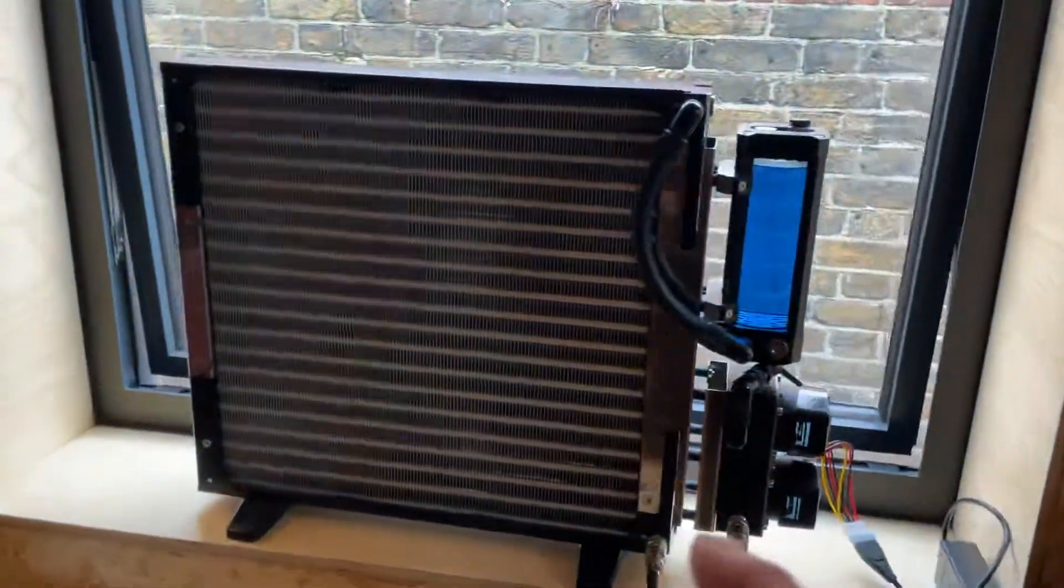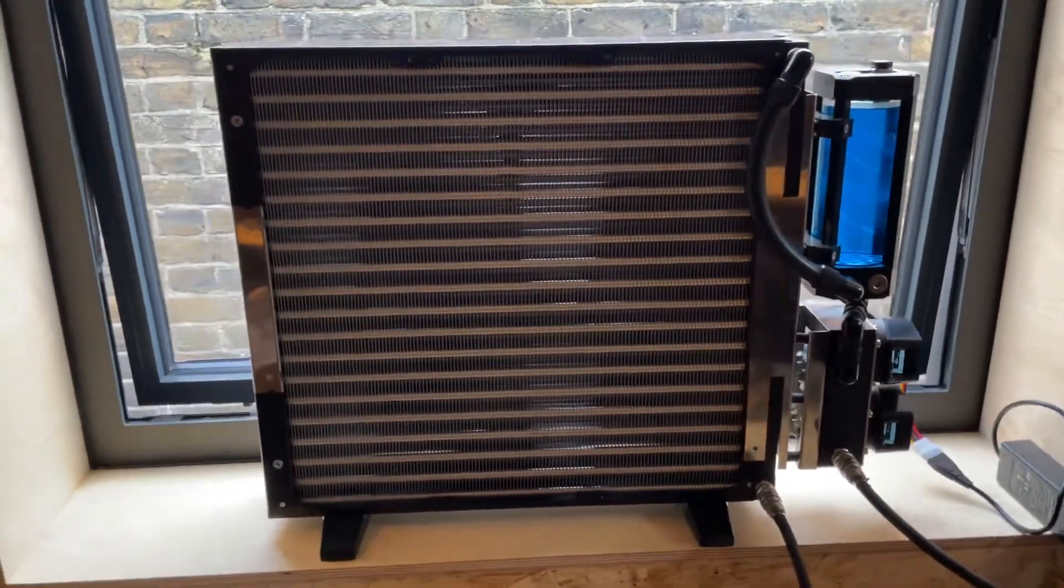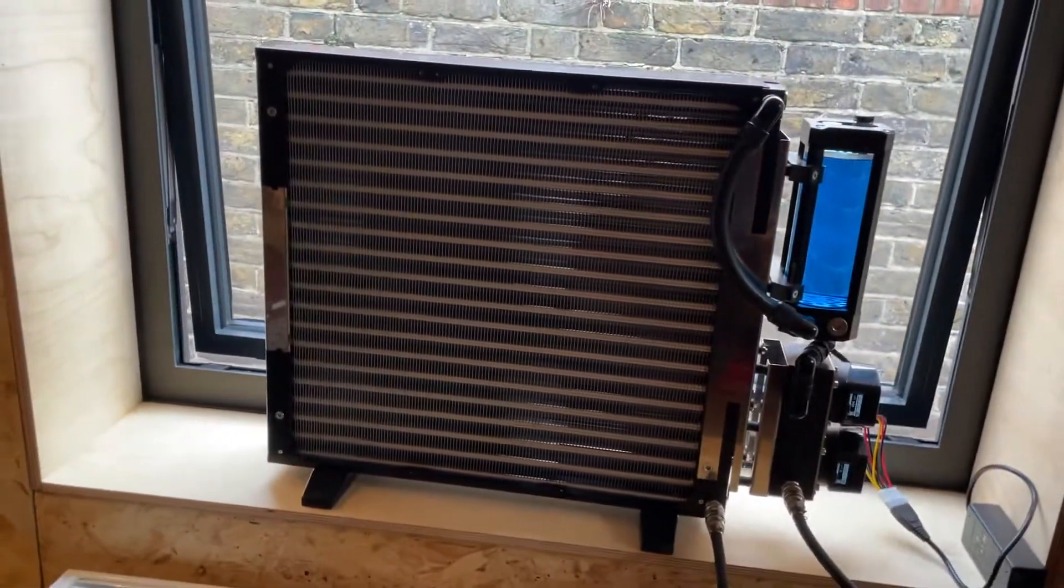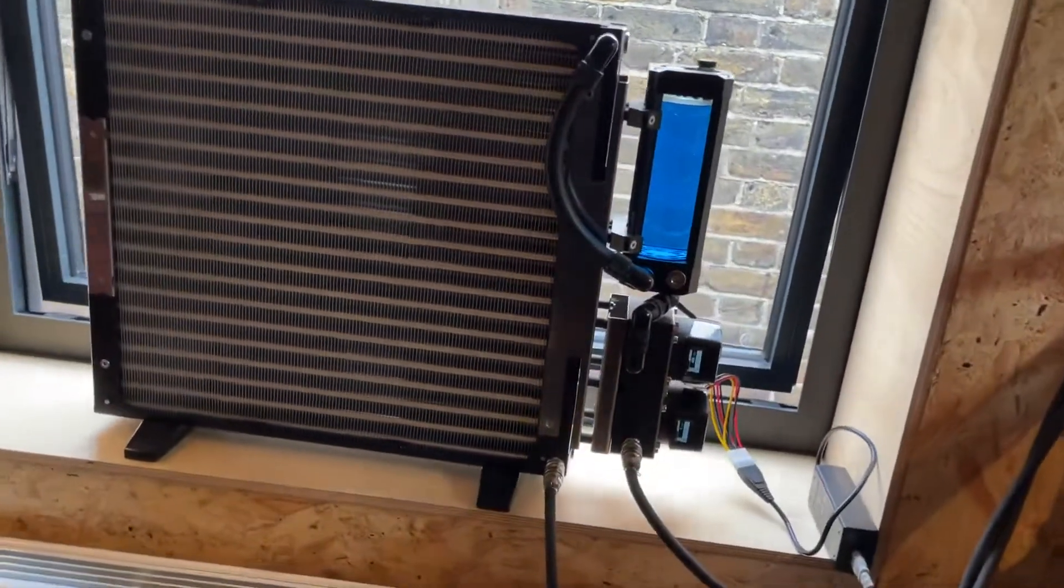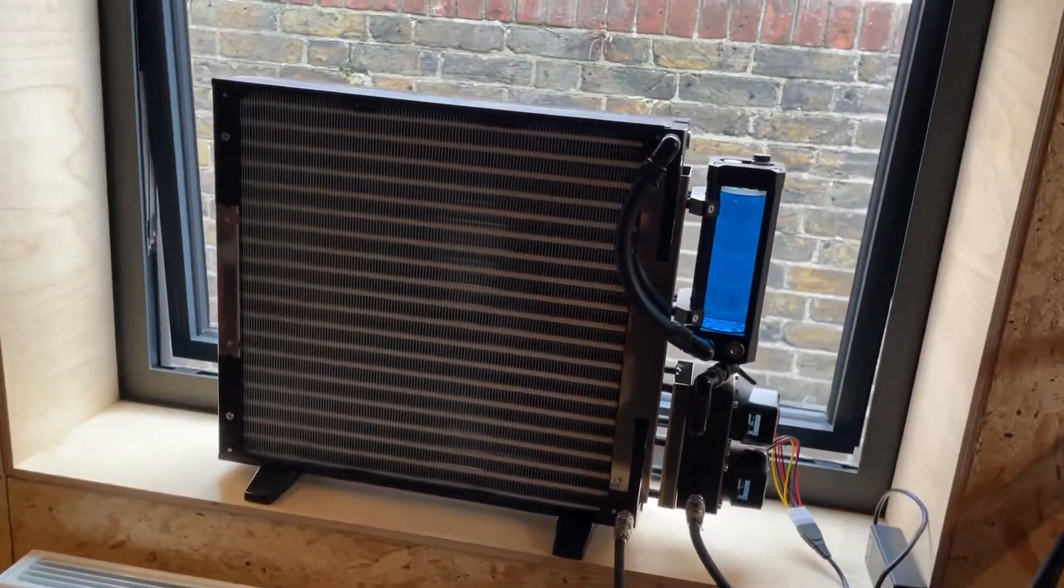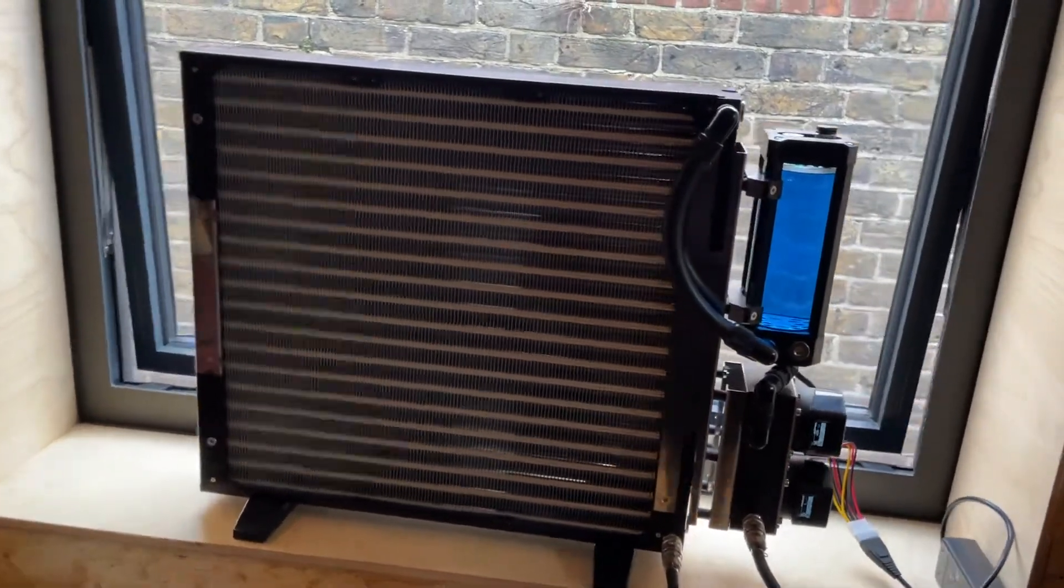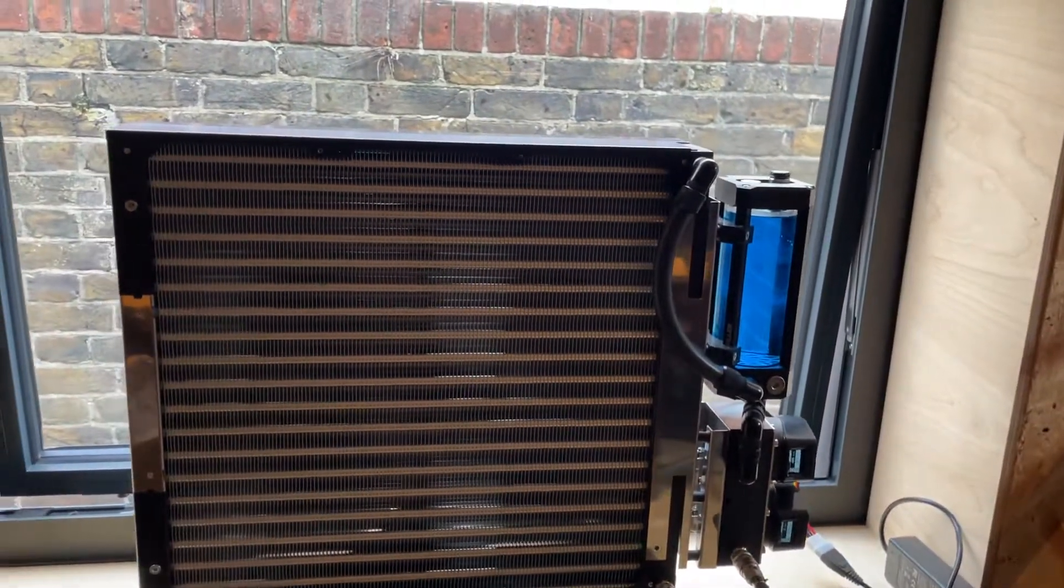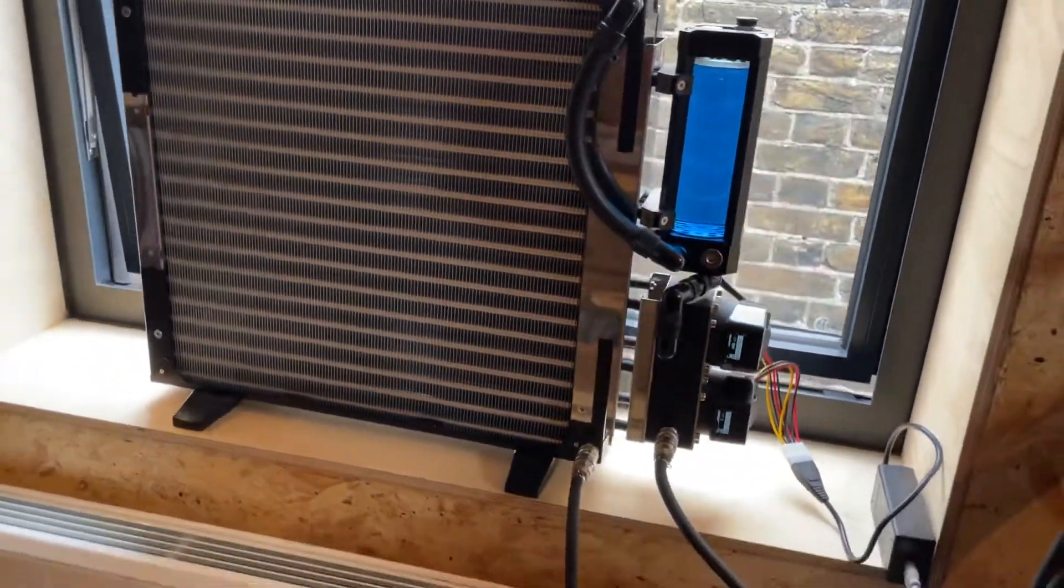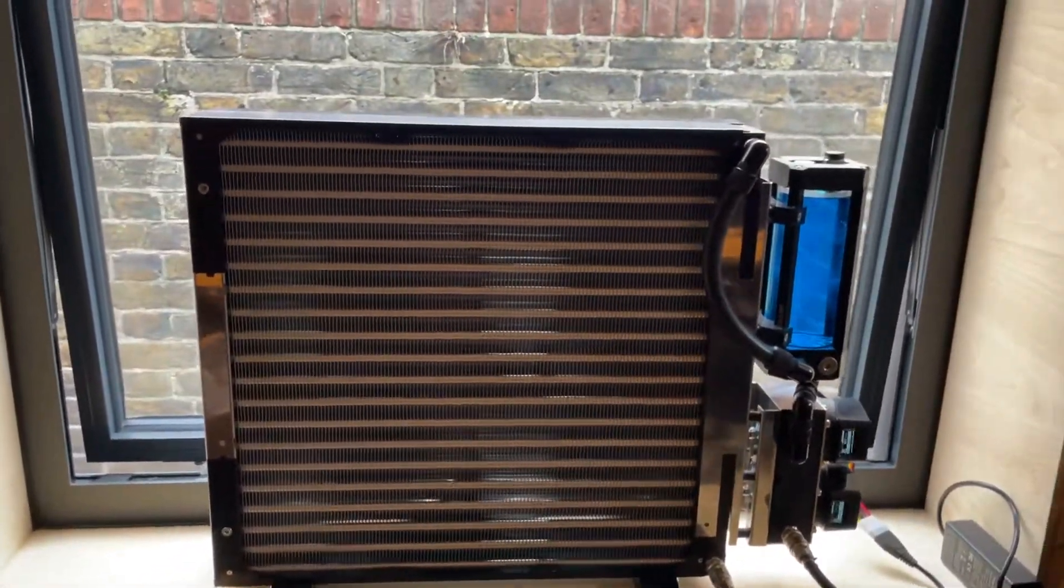It's just been really nice to be able to decouple them and get these kind of results. We're definitely sold on the solution. We're just going to button up all of the little bits that's going to make this different to maybe any of the solutions you can get at the moment. I mean, CoolIT makes a solution, but again it's using fans that go up to maybe 5000 RPM - it's a jet engine. This is 100% load - the noise that you can hear is the server in the background and we've got two other machines that are having burn-in tests at the moment.